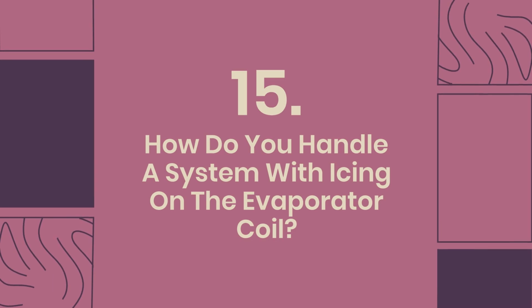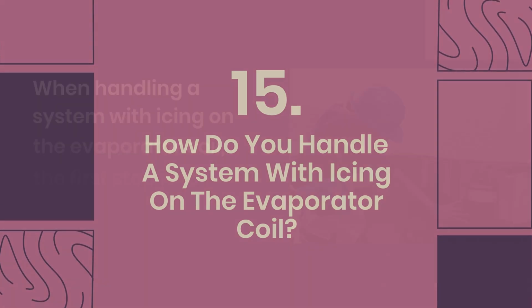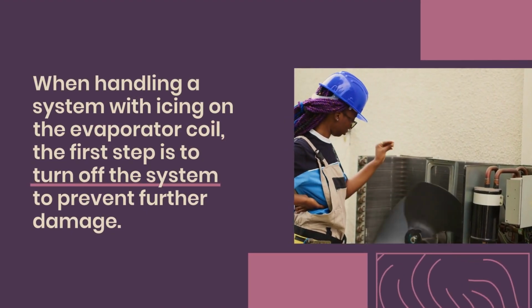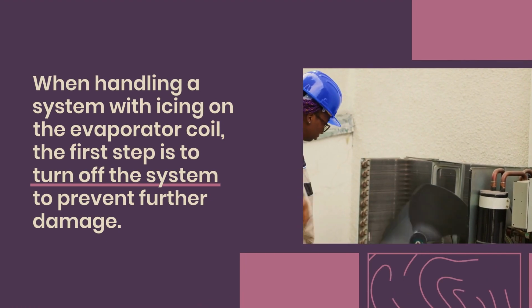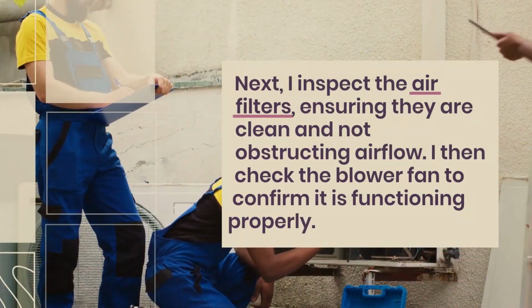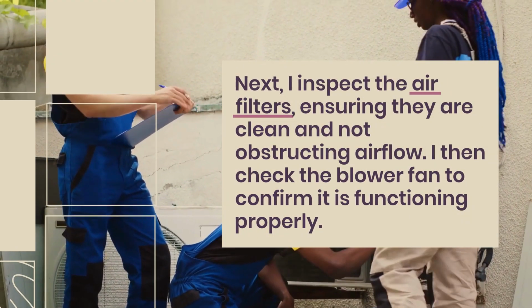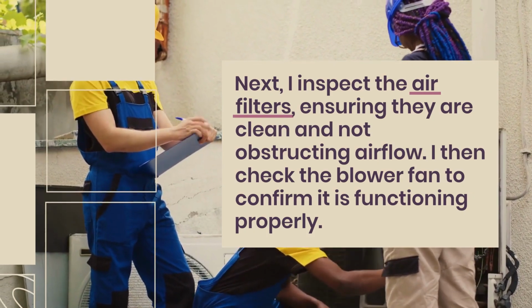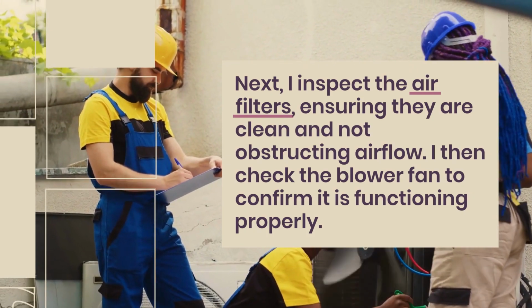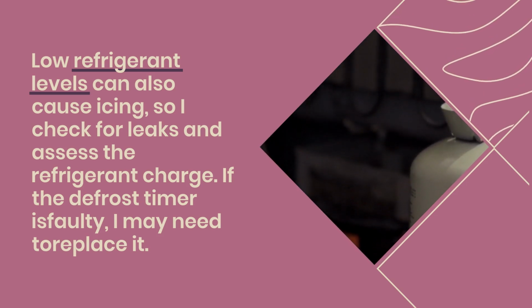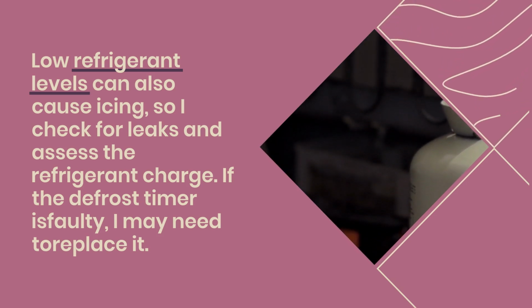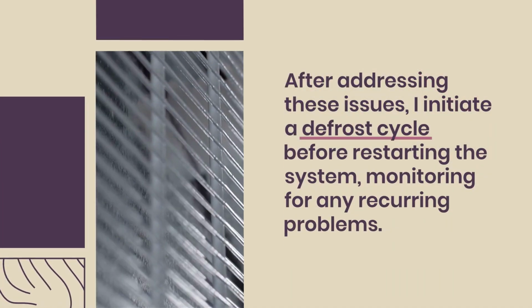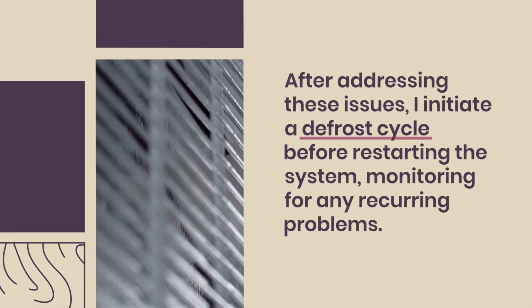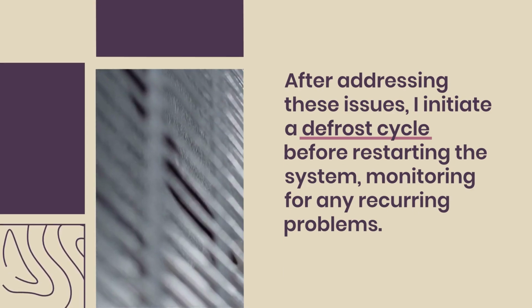15. How do you handle a system with icing on the evaporator coil? When handling a system with icing on the evaporator coil, the first step is to turn off the system to prevent further damage. Next, I inspect the air filters, ensuring they are clean and not obstructing airflow. I then check the blower fan to confirm it is functioning properly. Low refrigerant levels can also cause icing, so I check for leaks and assess the refrigerant charge. If the defrost timer is faulty, I may need to replace it. After addressing these issues, I initiate a defrost cycle before restarting the system, monitoring for any recurring problems.